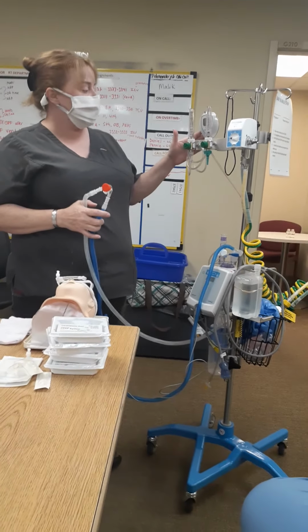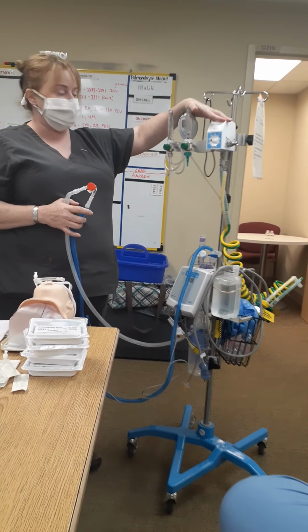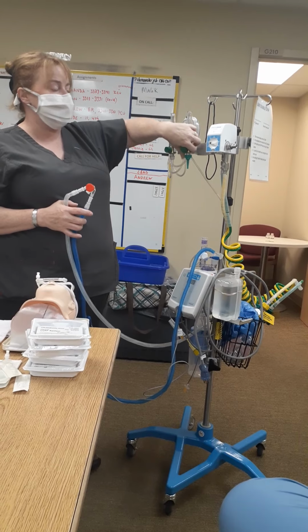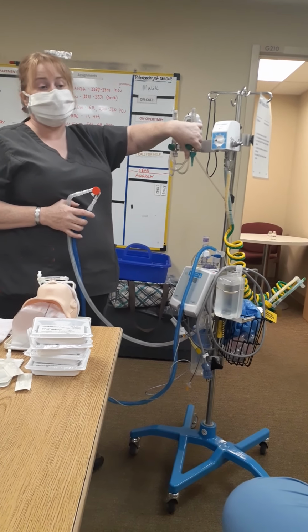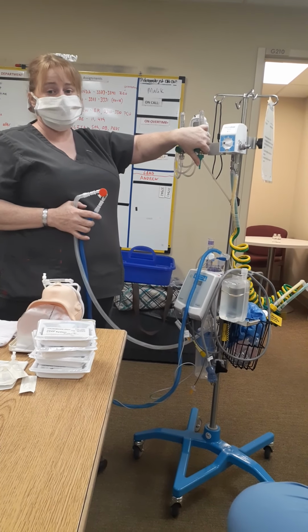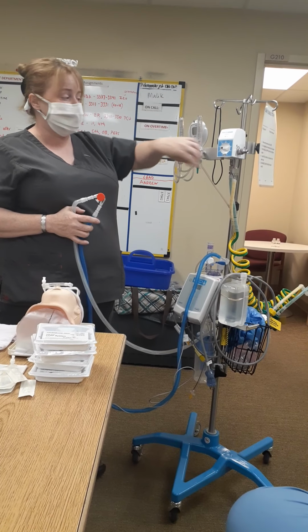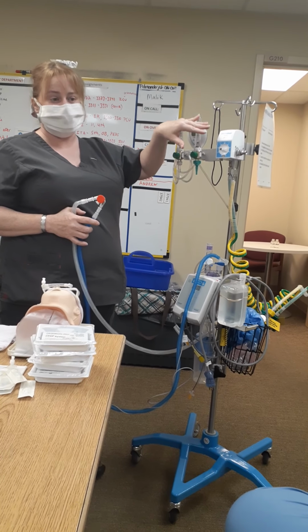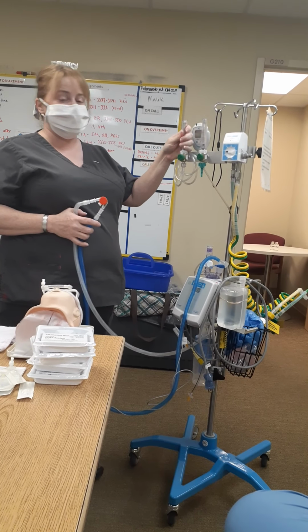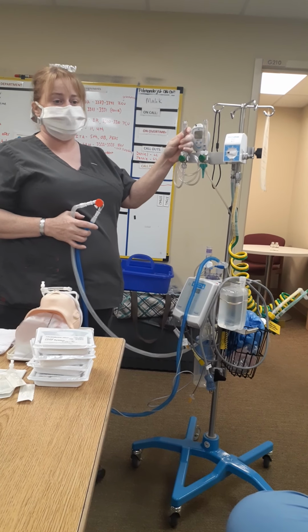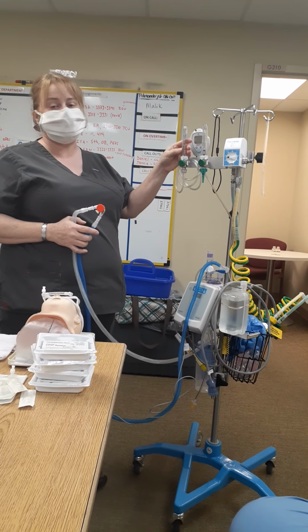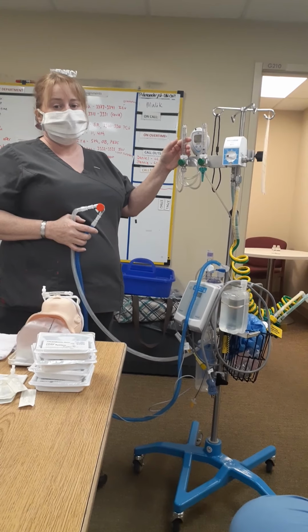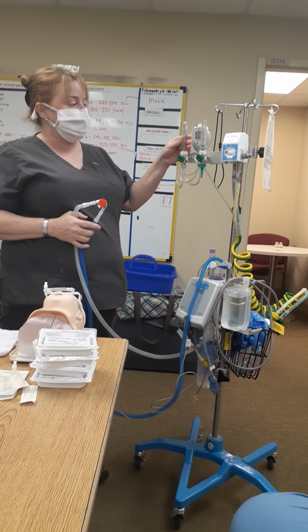So baby CPAP, this is our setup for the baby CPAP. This flow meter over here is for nasal cannula only. Don't use it for the CPAP. This only goes up to 3.5 liters. This flow meter over here on this side is the one that will be used for the CPAP, and it is always set to 8 liters per minute. Baby CPAP is always on 8.